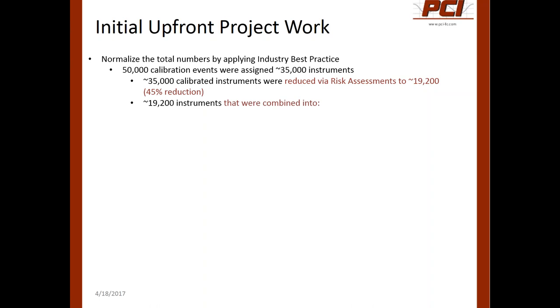Once we were able to reduce the total number of instruments via a risk assessment process, we decided to take a look at the way we calibrated instruments. Legacy practices calibrated instruments more on a per-instrument basis. We moved into a loop calibration model. When we did that, we were able to reduce from 19,200 instruments to 13,500 physical instrument loops, which we calibrated. That came out to about 21,600 events a year. So in total, we were able to reduce the number of calibration events by 57% of what was originally expected.